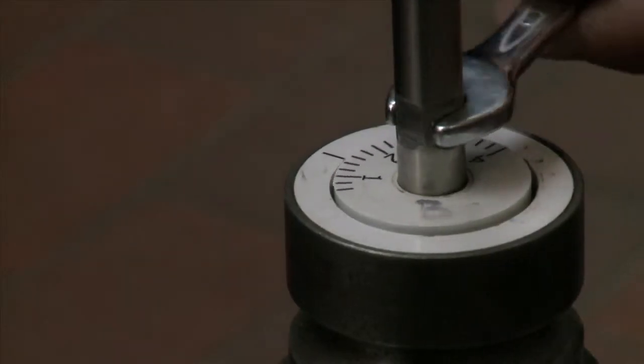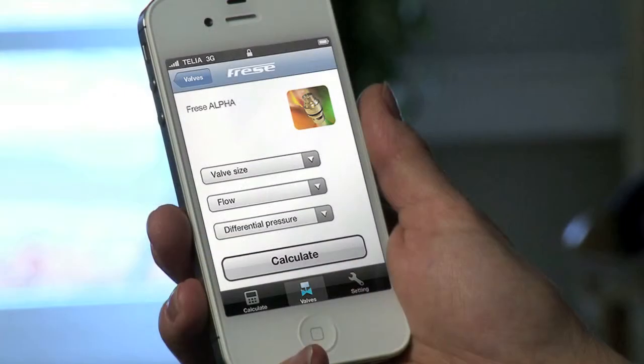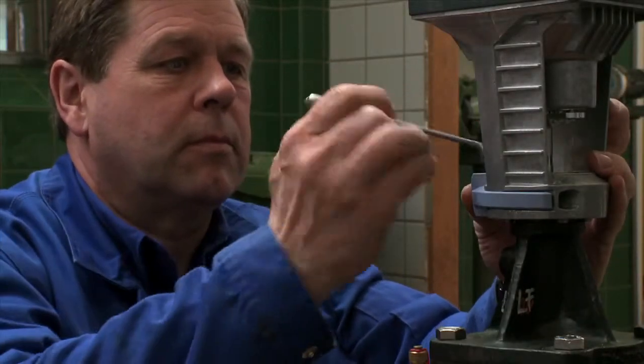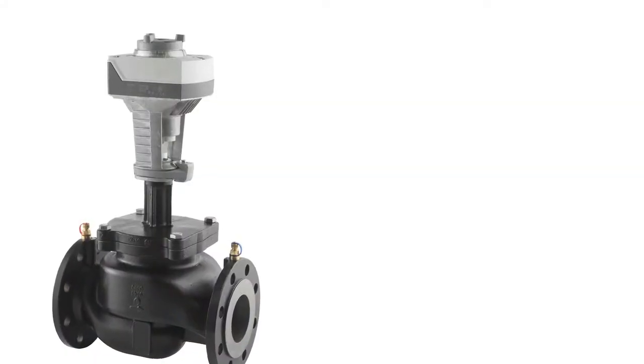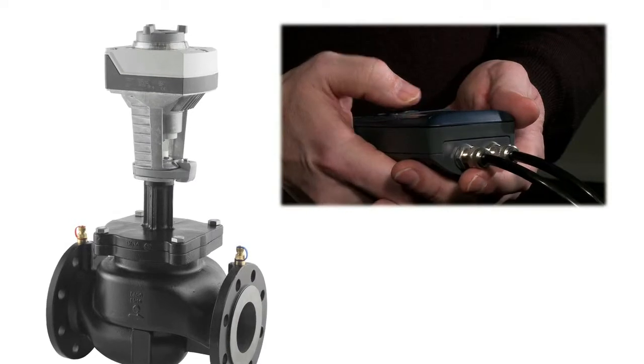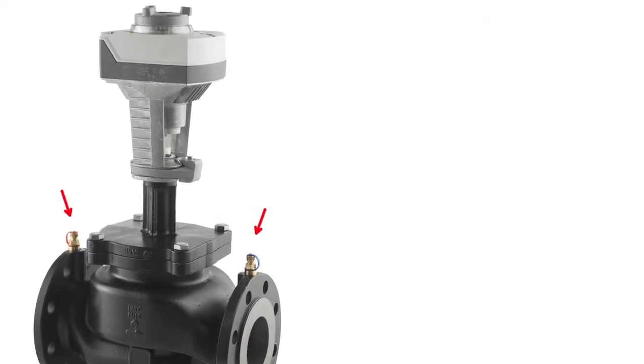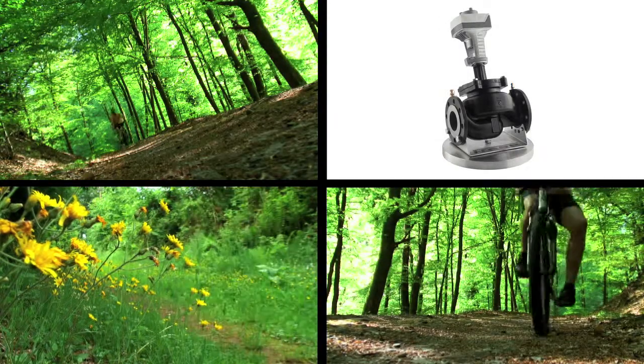Set the design flow on the valve according to the graph or software program QuickCalc, which can be downloaded to your computer or smartphone. Then mount the actuator and the valve is ready to use. To set the pump, check the differential pressure just within the pressure control range of the valve using the integral pressure plugs. Then energy consumption is optimised and the valve is ready for use.